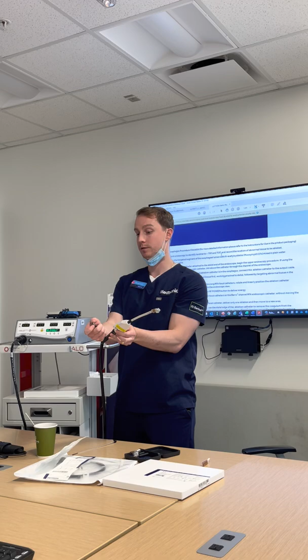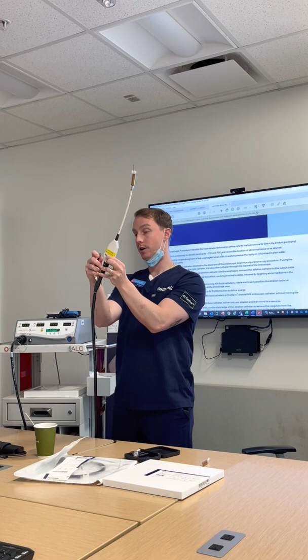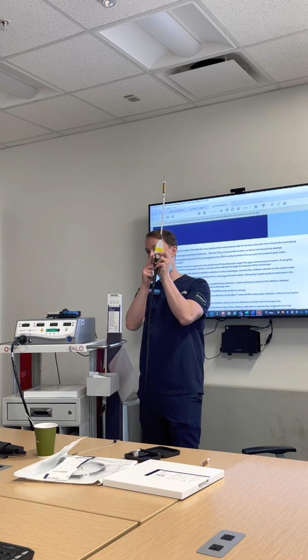There's going to be a plastic filter on this handle here. Again, there are a lot of turning collars on this system. So there's going to be a plastic filter. Please use your imagination because mine fell off. But what you'll do is connect this cord here to the filter here. This connection is typically where we're going to find an air leak most of the time. So if we click the auto inflate button and it says air leak in your status window here, this is typically where the air leak is happening: this cord is not fully tightened down to the filter, and/or the plastic filter isn't twisted all the way down either. So it's one of the two.